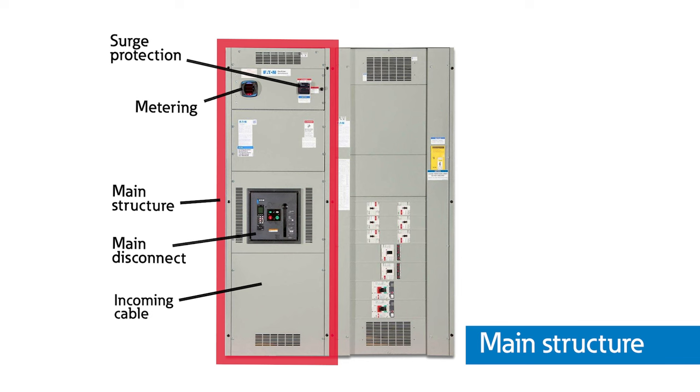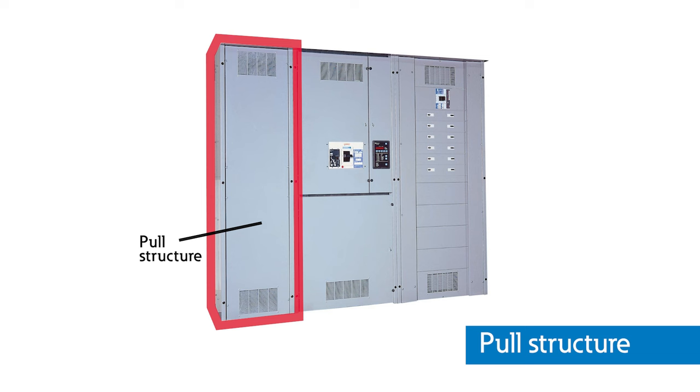A switchboard can consist of a single vertical structure or multiple structures depending on the number and sizes of the loads being powered. A main structure will contain the main disconnects or main lugs and will often contain utility and/or customer metering equipment and surge protection. Cabling can enter directly into the main structure or through a dedicated pull structure, which is a blank enclosure containing empty space through which cabling can be pulled, commonly used in service entrance switchboards.